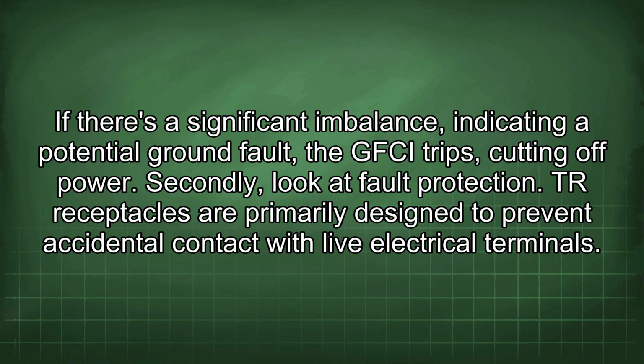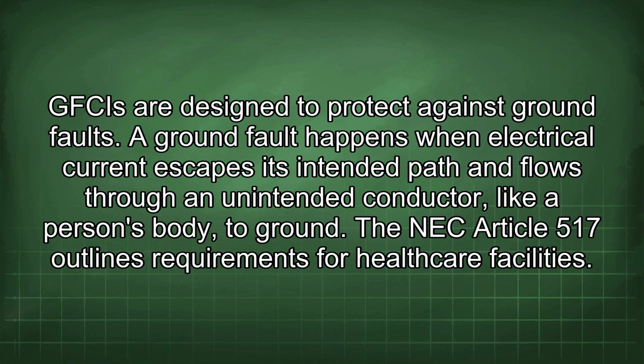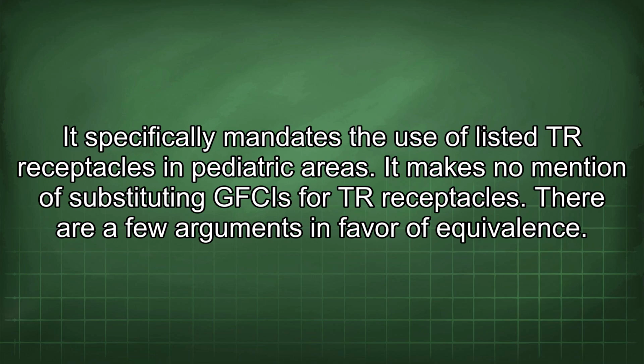Secondly, look at fault protection. TR receptacles are primarily designed to prevent accidental contact with live electrical terminals. GFCIs are designed to protect against ground faults. A ground fault happens when electrical current escapes its intended path and flows through an unintended conductor, like a person's body, to ground. The NEC Article 517 outlines requirements for healthcare facilities. It specifically mandates the use of listed TR receptacles in pediatric areas. It makes no mention of substituting GFCIs for TR receptacles.